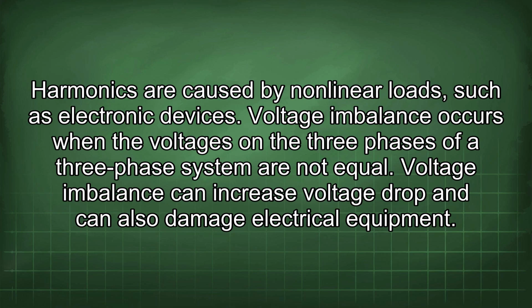Voltage imbalance occurs when the voltages on the 3 phases of a 3-phase system are not equal. Voltage imbalance can increase voltage drop and can also damage electrical equipment.